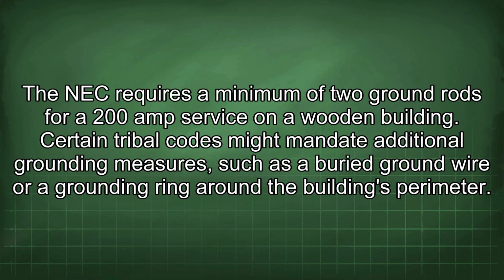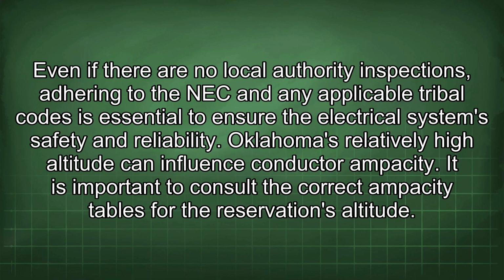The NEC requires a minimum of 2 ground rods for a 200 amp service on a wooden building. Certain tribal codes might mandate additional grounding measures such as a buried ground wire or a grounding ring around the building's perimeter. Even if there are no local authority inspections, adhering to the NEC and any applicable tribal codes is essential to ensure the electrical system's safety and reliability.